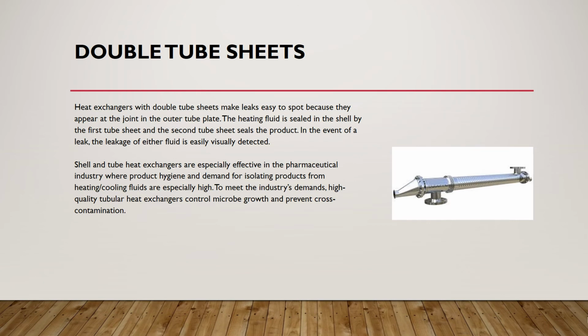Heat exchangers with double tube sheets make leaks easy to spot because they appear at the joint in the outer tube plate. The heating fluid is sealed in the shell by the first tube sheet, and the second tube sheet seals the product. In the event of a leak, the leakage of either fluid is easily visually detected.